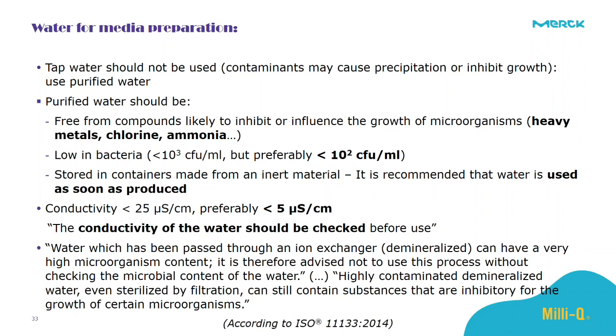The conductivity also should be less than 5 microsiemens. The conductivity of the water should be checked before use, and this is a very important point. Water which has been passed through an ion exchanger can have very high microorganism content. Take care. It is therefore advised not to use this process without checking the microbial content of the water itself. Highly contaminated demineralized water, even if sterilized by filtration, can still contain substances that are inhibitory for the growth of certain microorganisms.